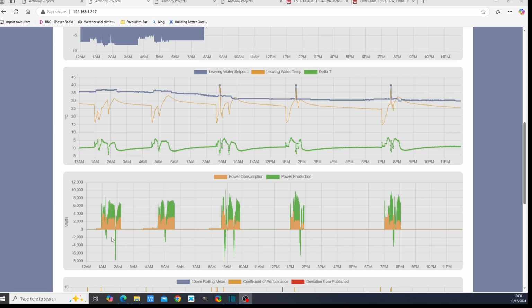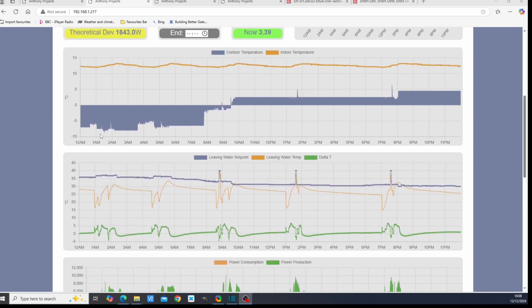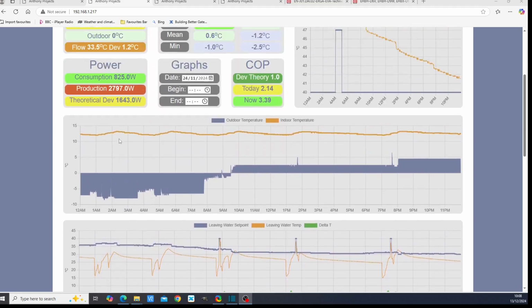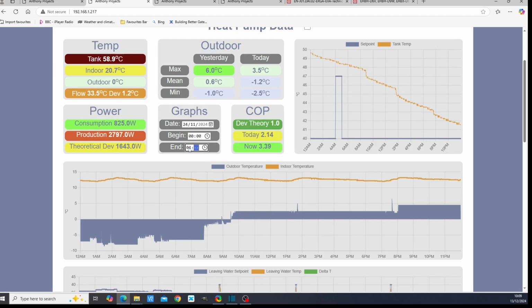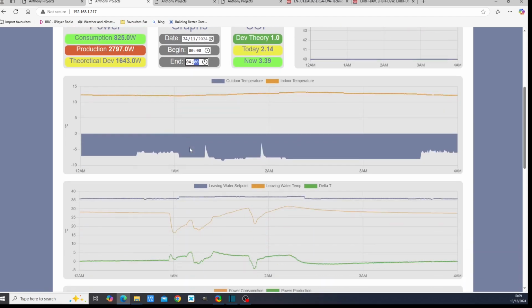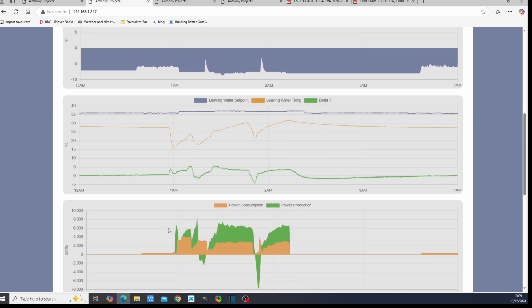But anyway, let's have a look at this regime here from 1 a.m. to 2 a.m. and then 0400. Here we go. So what you can see here, first of all, is that we get some produced heat from the heat pump. And then it says, oh, it's too cold. And why is it doing this? Why is the heat pump coming in and then coming off and then reverting to backup heater here? Because this is pretty much 3 kilowatts exactly, 3.5 kilowatts. That's your backup heater. That's your 13 amps.